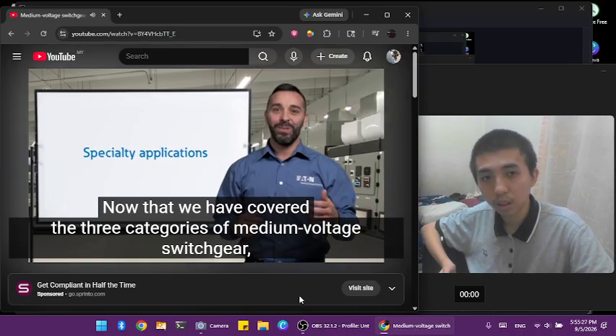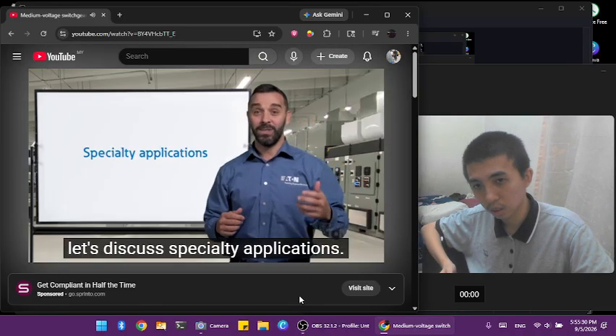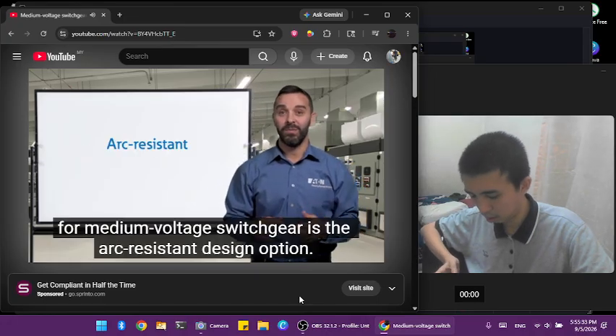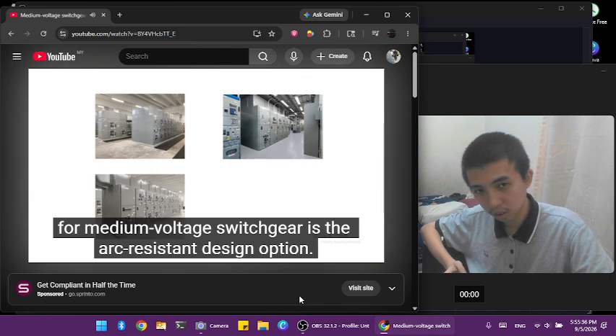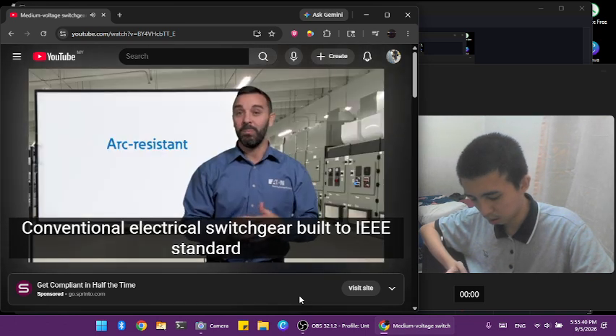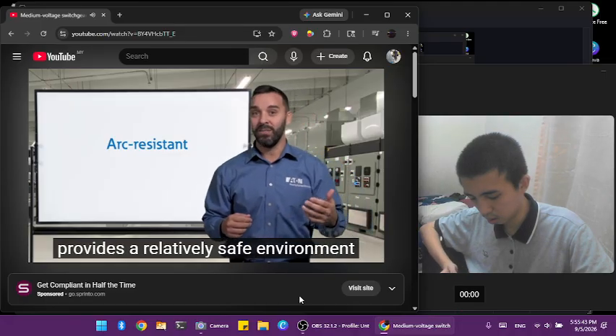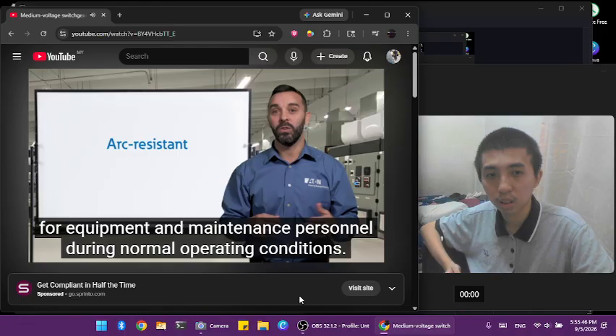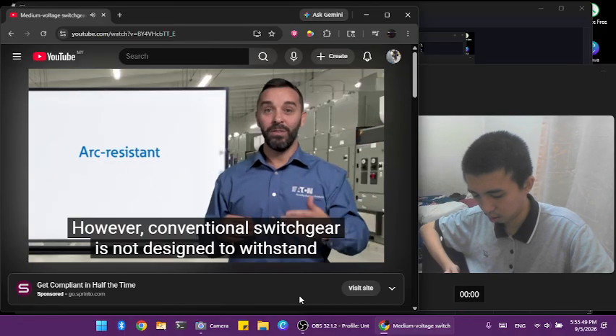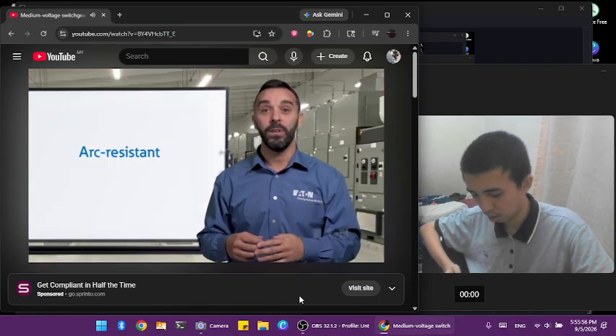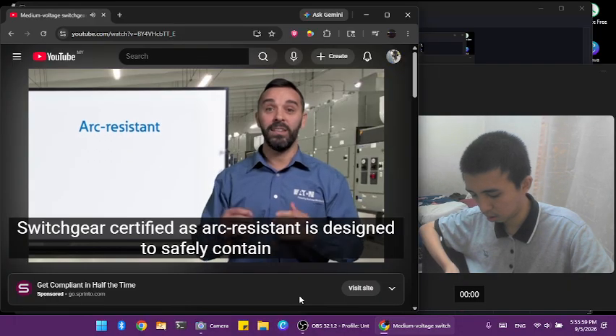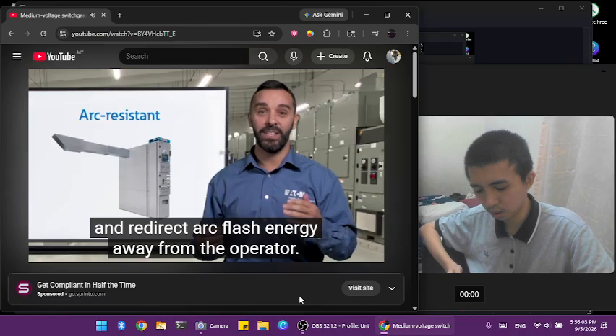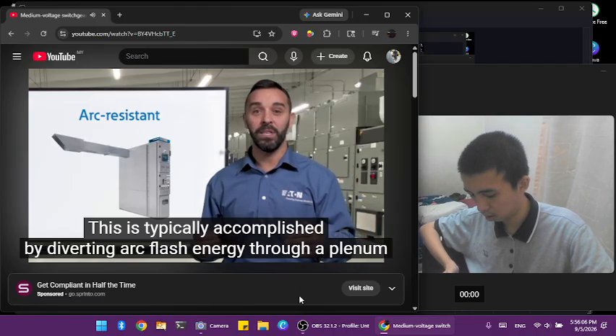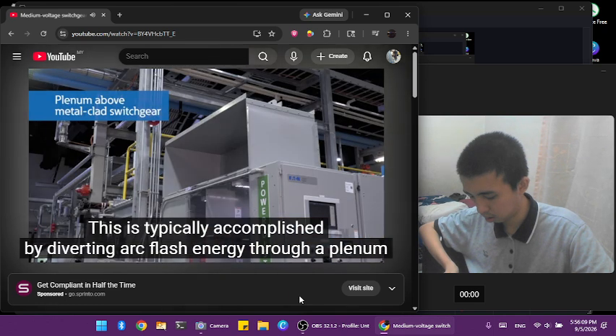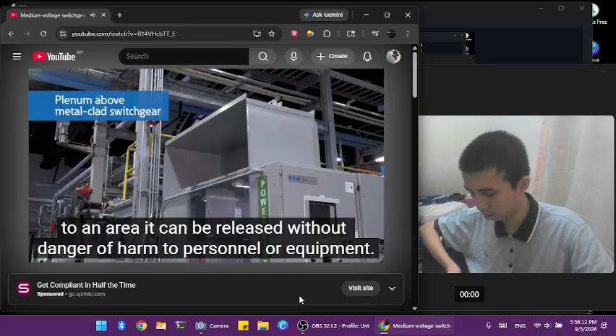Now that we've covered the 3 categories of medium voltage switchgear, let's discuss specialty applications. An important safety feature for medium voltage switchgear is the arc-resistant design option. Conventional electrical switchgear built to IEEE standard provides a relatively safe environment for equipment and maintenance personnel during normal operating conditions. However, conventional switchgear is not designed to withstand the enormous energy released during an electrical fault condition. Switchgear certified as arc resistant is designed to safely contain and redirect arc flash energy away from the operator. This is typically accomplished by diverting arc flash energy through a plenum to an area it can be released without danger of harm to personnel or equipment.